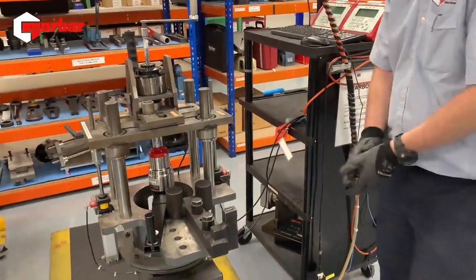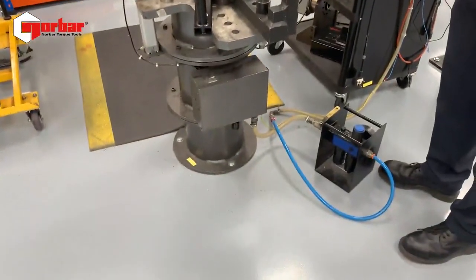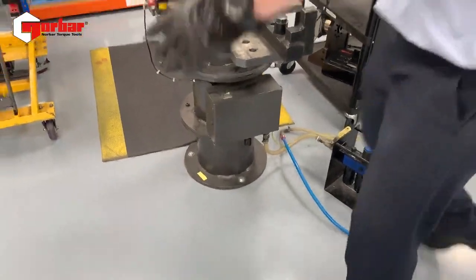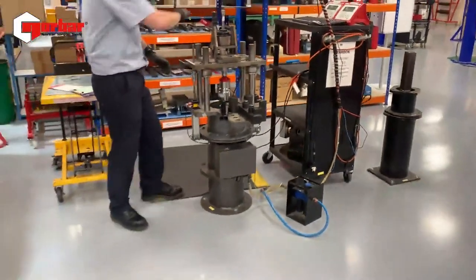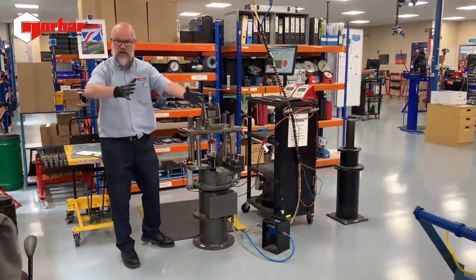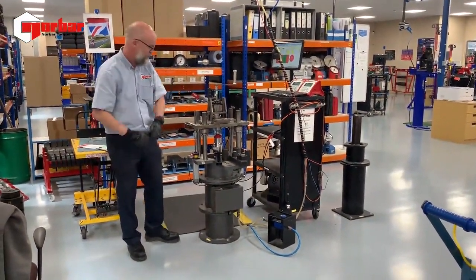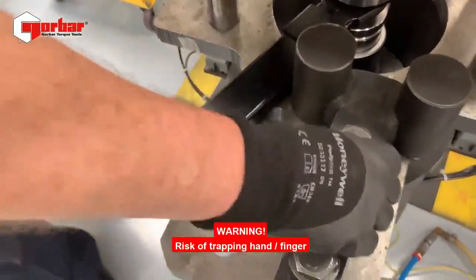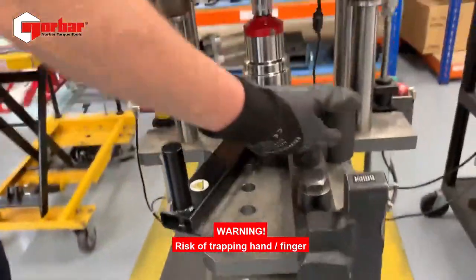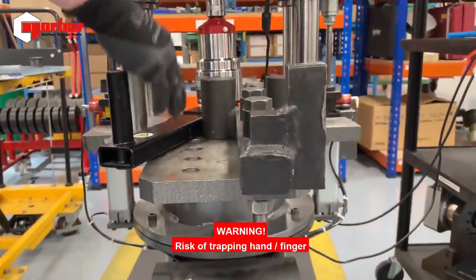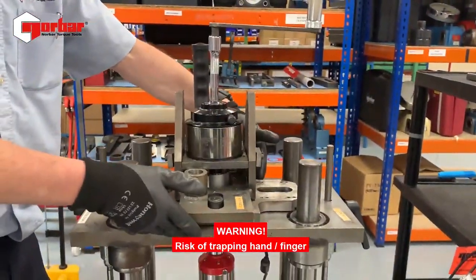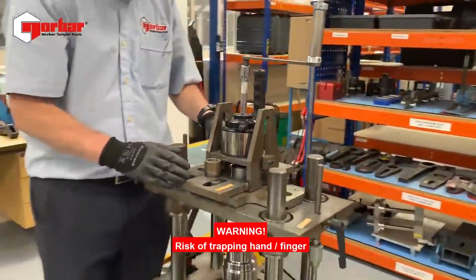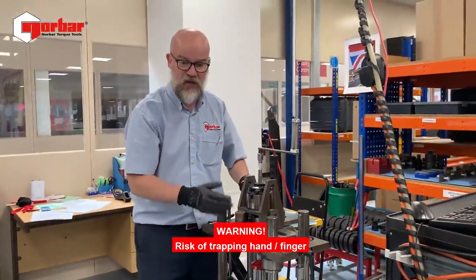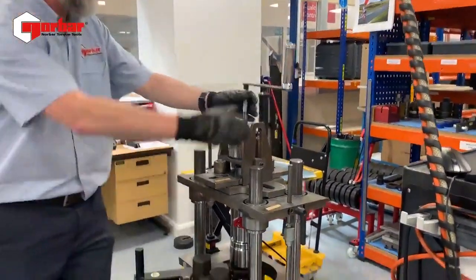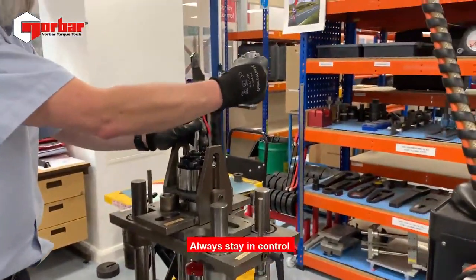So the rig itself, let's recap. The rig is bolted to the floor. When we bolt it to the floor, we ensure that it's positioned so that you've got a good working area. Okay. What we don't want to be doing is operating the crank with a colleague working in close proximity, and there's a risk of impact. We've got numerous pinch points. There's reaction points here. Reaction points here. These reaction points are movable, so if you're doing counterclockwise or clockwise calibrations, you can move these points. You've got potential pinch hazards here. Okay, you need to be mindful, and you need to be well read of the manual to understand what those pinch points are. Again, when we're releasing a load, we keep hold of our crank handle.